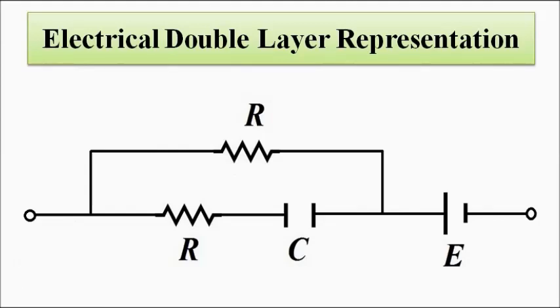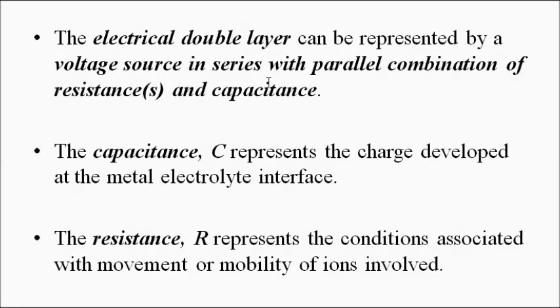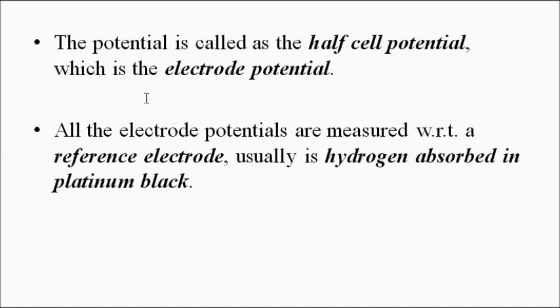The simplest representation of this electrical double layer consists of a voltage source representing the double layer potential, in series with a parallel combination of resistance and capacitance. The capacitance represents the charge developed at the metal-electrolyte interface, and the resistance represents the conduction properties — specifically the mobility of ions and how easily biosignals can conduct through this charge layer to reach the electrode.